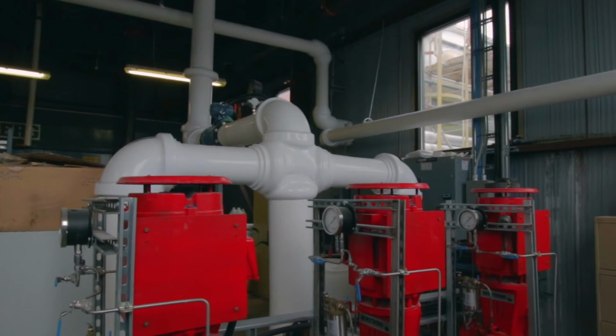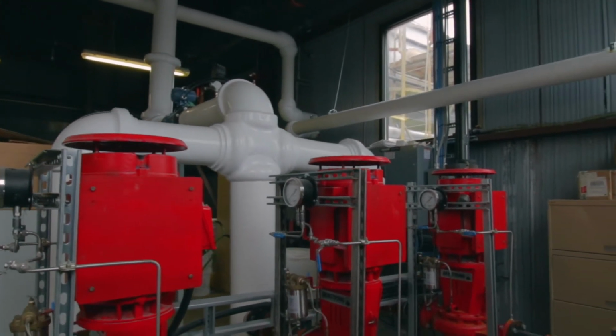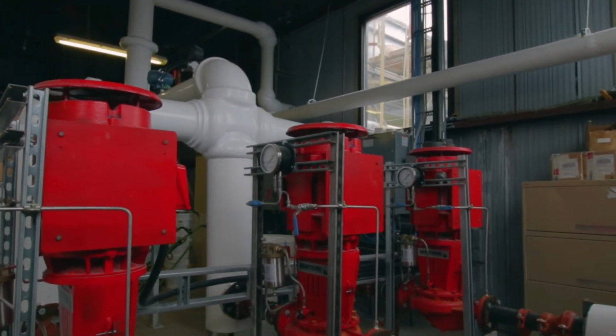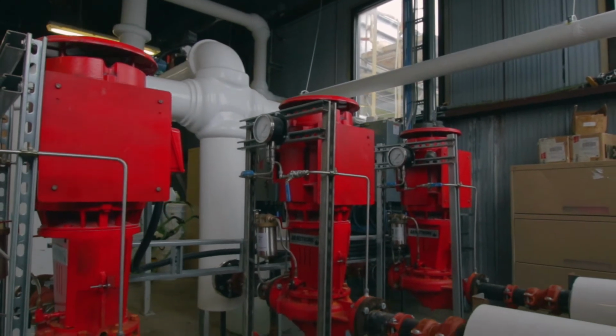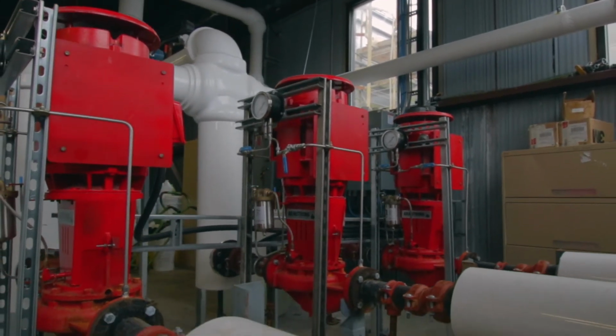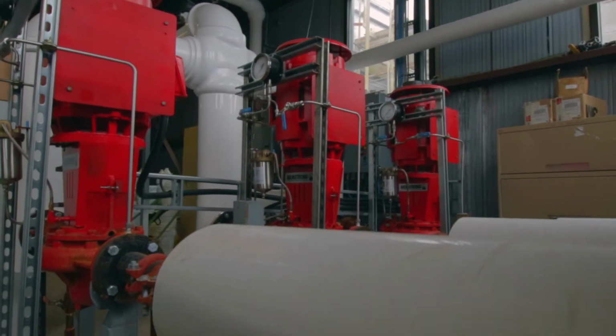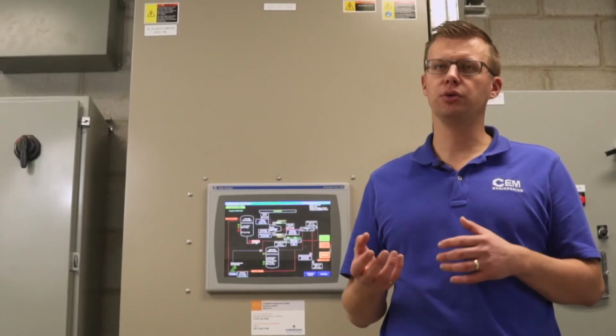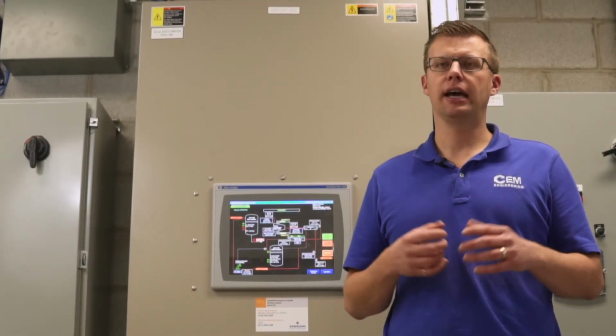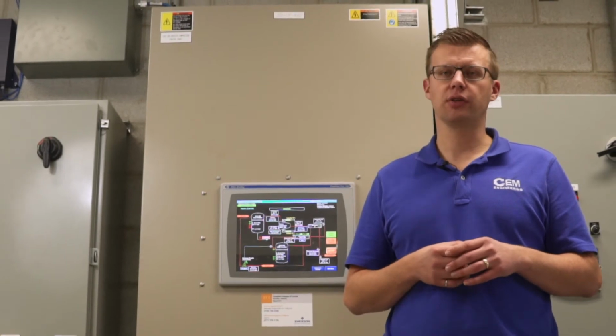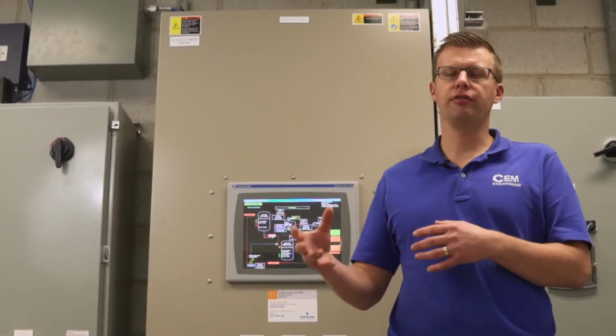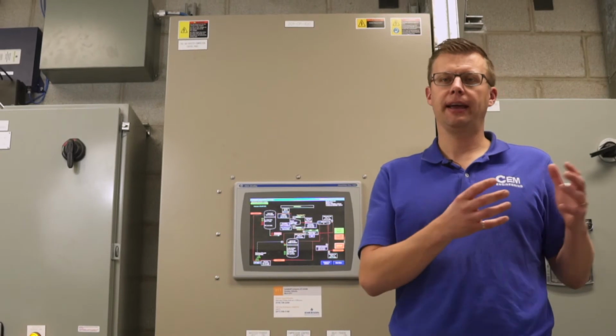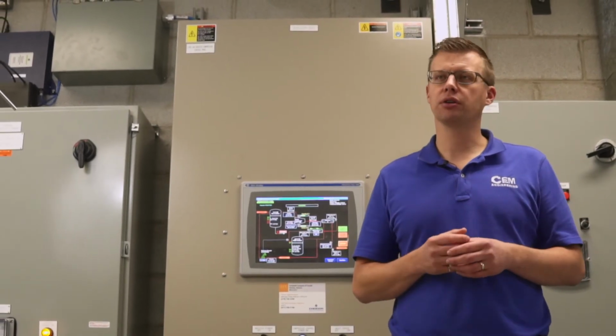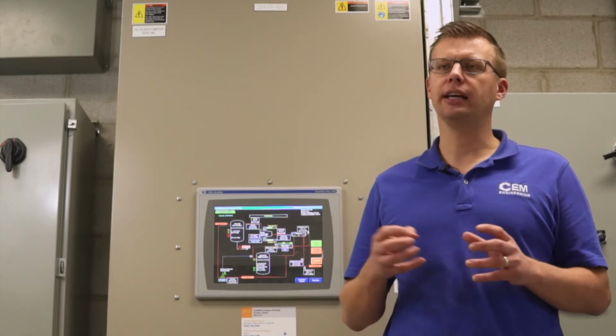After the implementation of the Co Gen, Campbell's put in a reverse osmosis system to treat water that they're using elsewhere in the process and make it suitable for boiler feed water. This really allowed them to drive a lot of savings in terms of their water use and their water disposal costs, and it made the system overall more efficient. And so that system provides them all the feed water they need for the boilers, and it's coming from a recaptured water source.